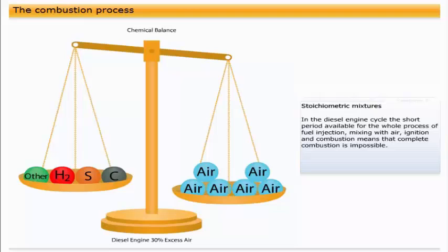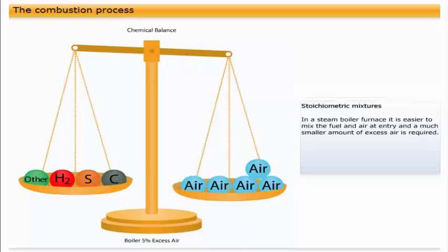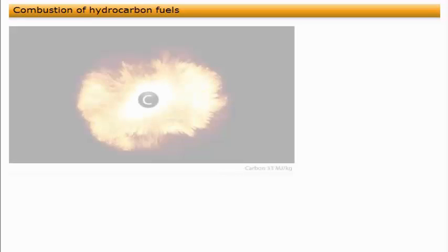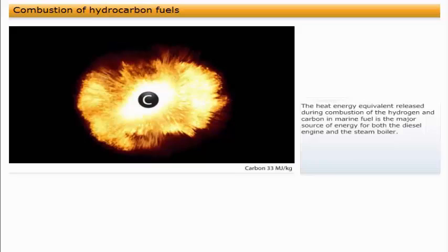In the diesel engine cycle, the short period available for the whole process of fuel injection, mixing with air, ignition, and combustion means that complete combustion is impossible. For the fuel combustion to be as complete as practically possible, air in excess of the stoichiometric amount is needed. This may be as much as 30% more than the ideal minimum. In a steam boiler furnace, it is easier to mix the fuel and air at entry, and a much smaller amount of excess air is required.